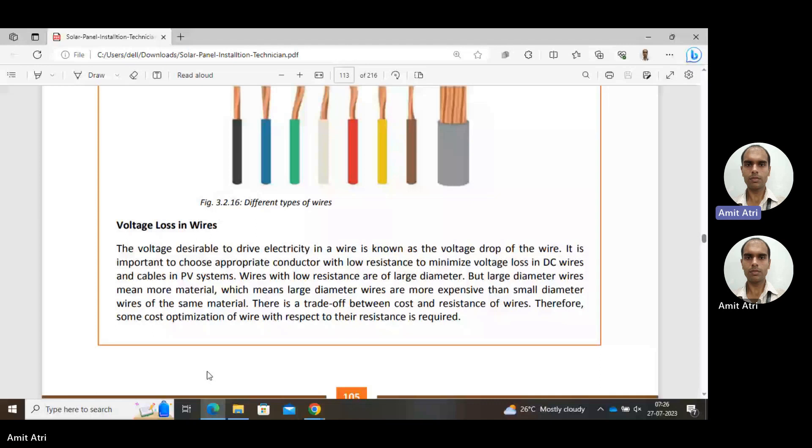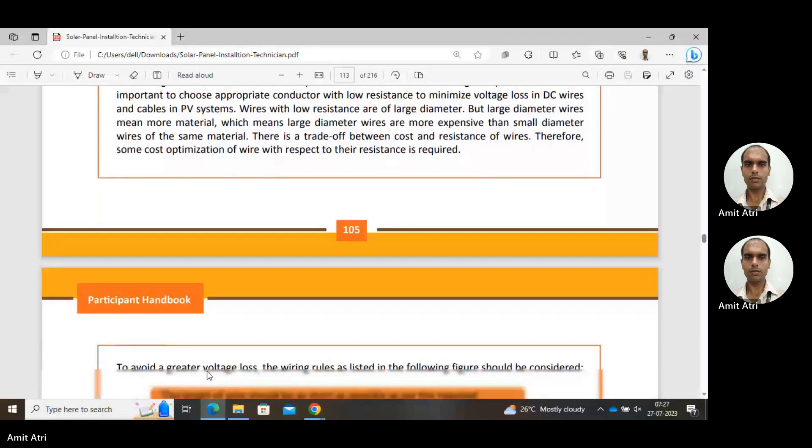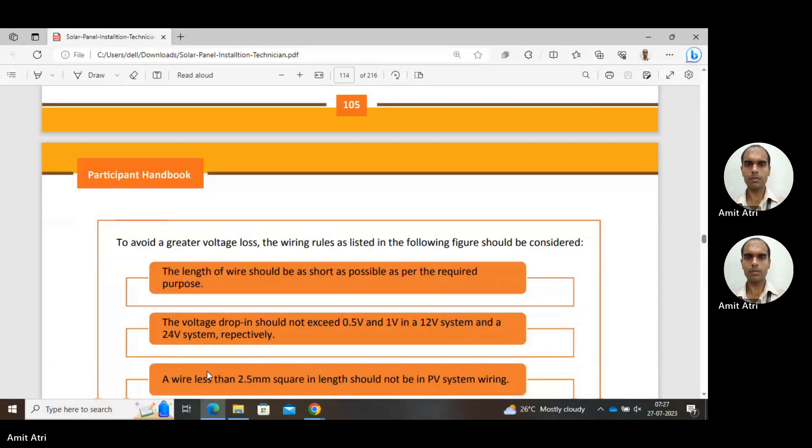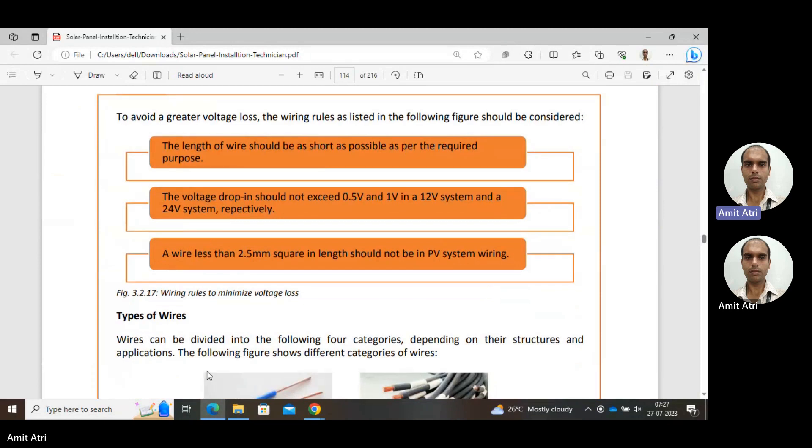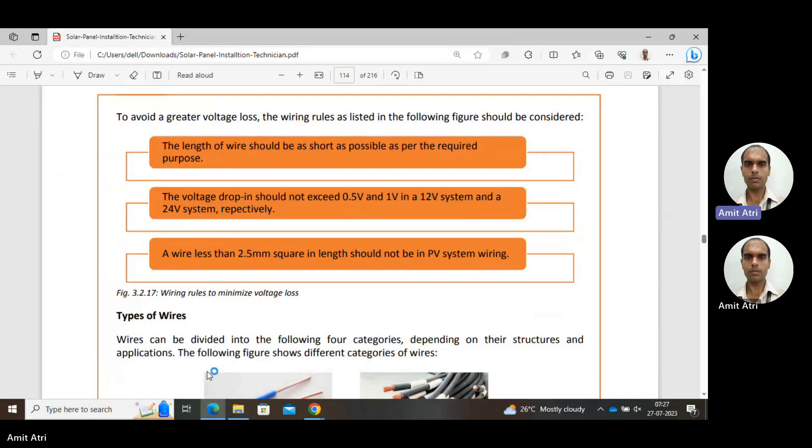To avoid greater voltage loss, the wiring rules are: the length of wire should be as short as possible as per the required purpose. No need to take a very long wire because resistance will be more and losses will be more. The voltage drop should not exceed 0.5 volt when operating in 12 volt system and should not exceed 1 volt if we are operating in 24 volt system. A wire less than 2.5 mm² in area should not be used in PV system wiring.